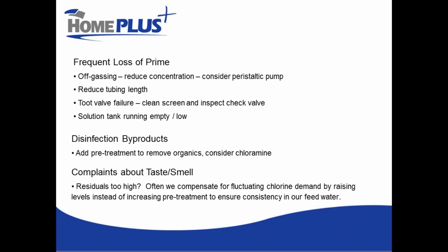And that can cause the pump to lose prime and stop pumping. Peristaltic pumps tend to have a little bit less problem with this, but generally, if you can reduce your concentration and inject more frequently with less pauses and a weaker solution, you will reduce your risk of off-gassing. You can also reduce the length of tubing. You could have foot valve failure. Definitely clean your foot valve.